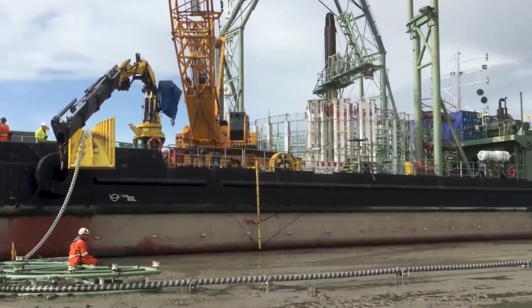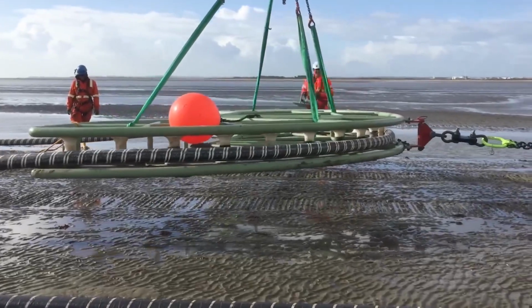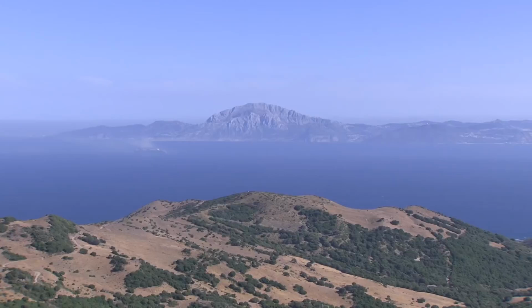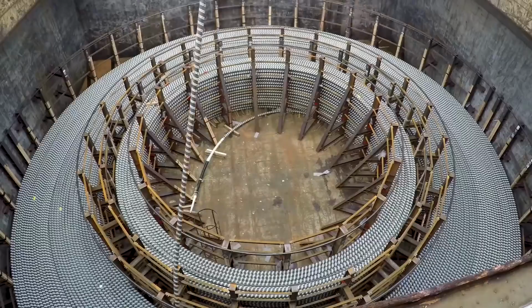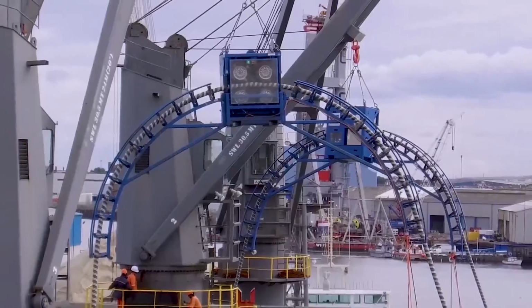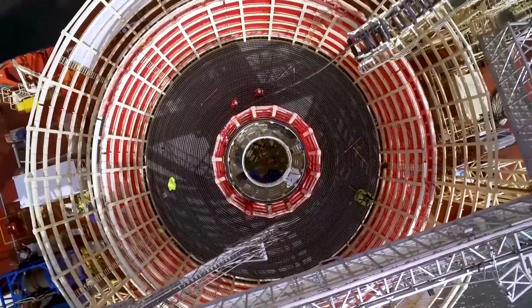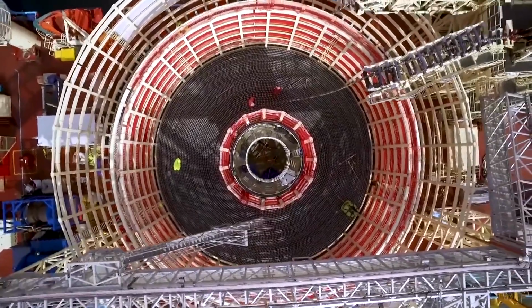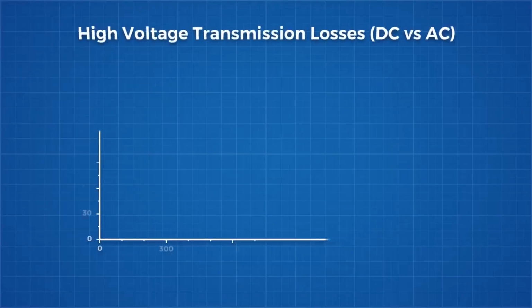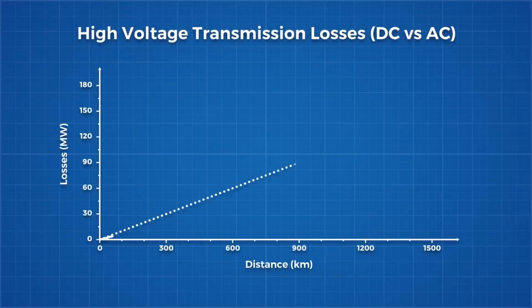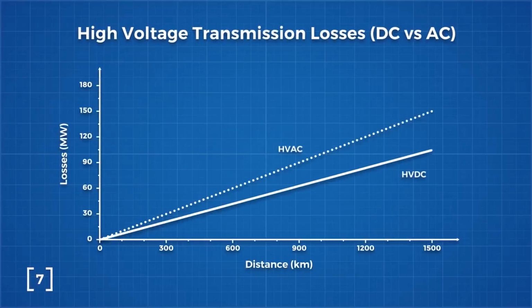This investment would go into both high-voltage alternating current transmission over shorter gaps, like those from Morocco to Spain, and high-voltage direct current over longer distances. There is a critical distance where high-voltage alternating current transmission does not make sense. If we plot transmission losses per kilometer for AC and DC transmission, it would look something like this, with DC losing less power per kilometer.